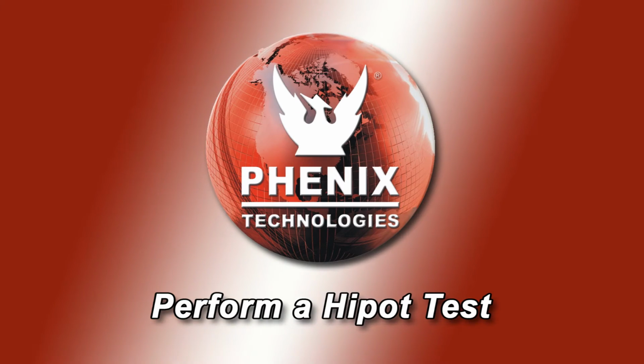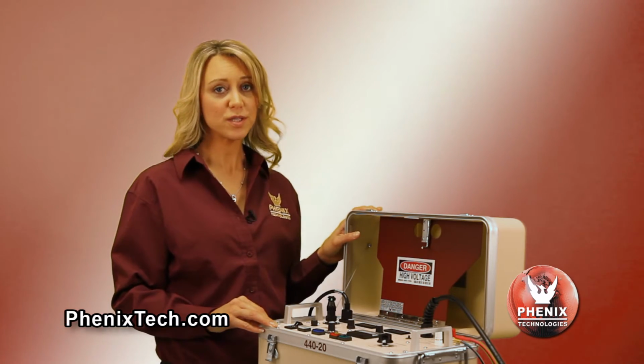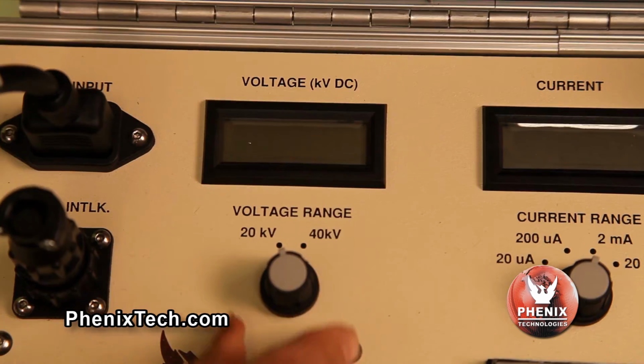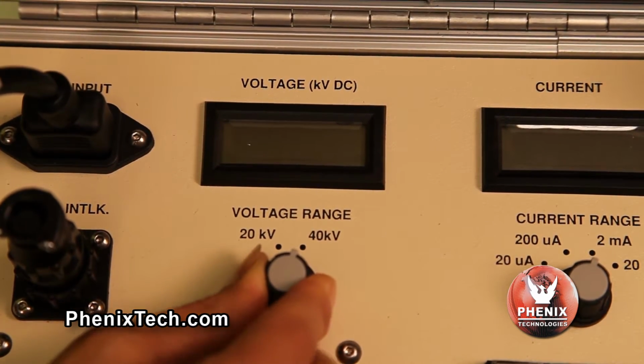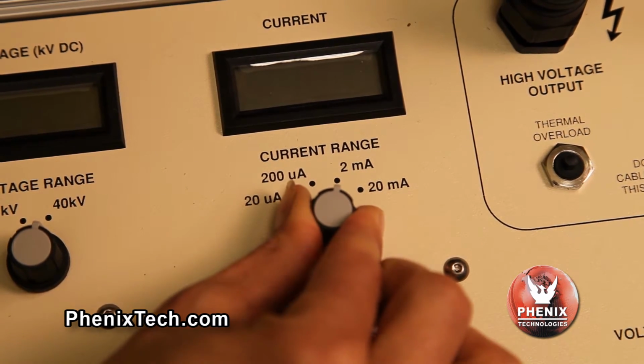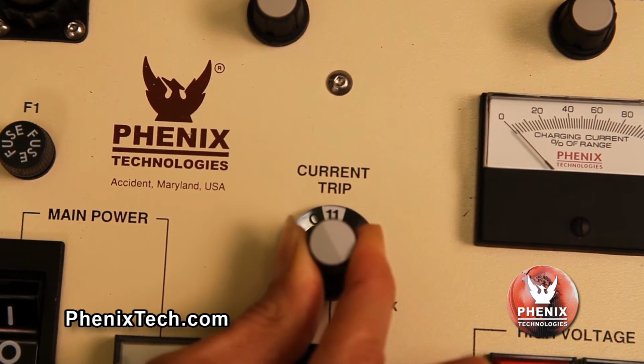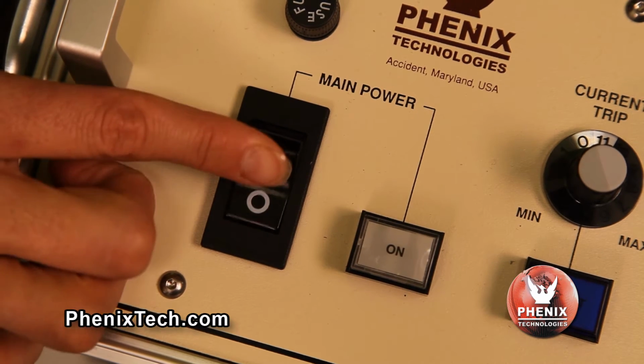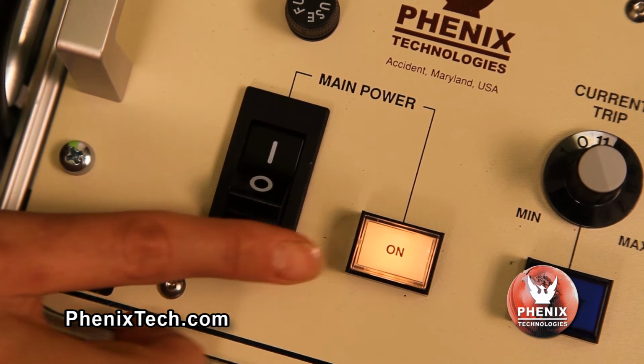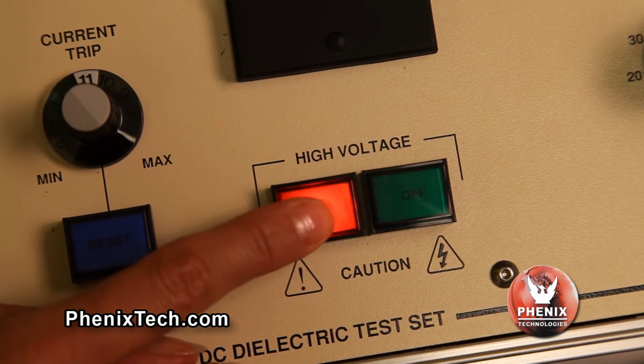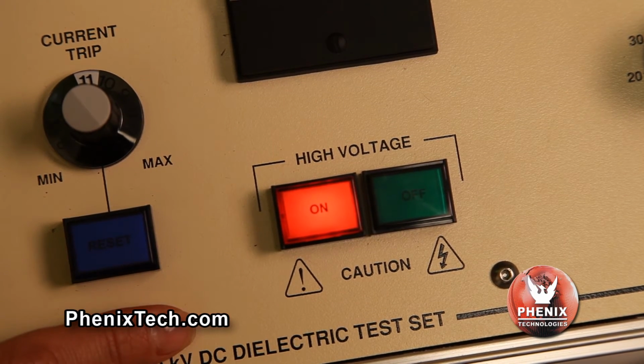Performing an actual Hipot test. Check that the voltage control is set to 0. Select the proper voltmeter range, desired current meter range, and desired trip level for current range selected. Turn on the control main power switch. The power on lamp will illuminate. Momentarily press the HV on push button. High voltage will be applied to the test specimen and the HV on light will illuminate.